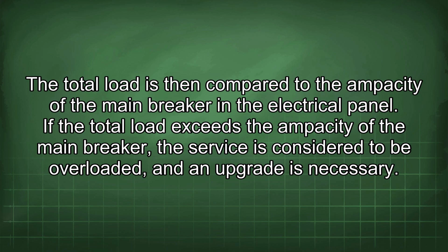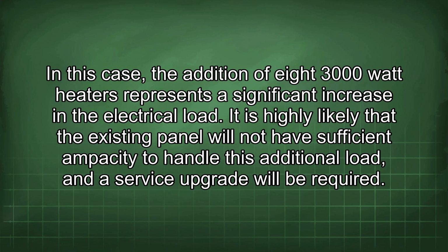upgrade is necessary. In this case, the addition of 8 3000-watt heaters represents a significant increase in the electrical load. It is highly likely that the existing panel will not have sufficient ampacity to handle this additional load, and a service upgrade will be required.